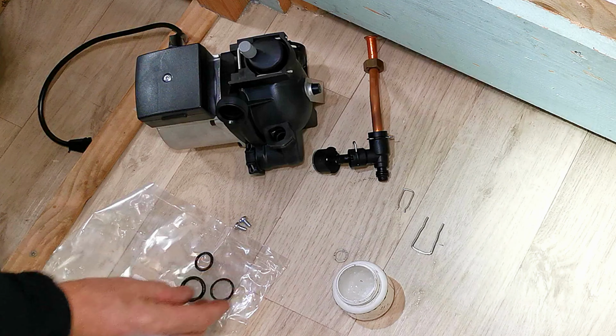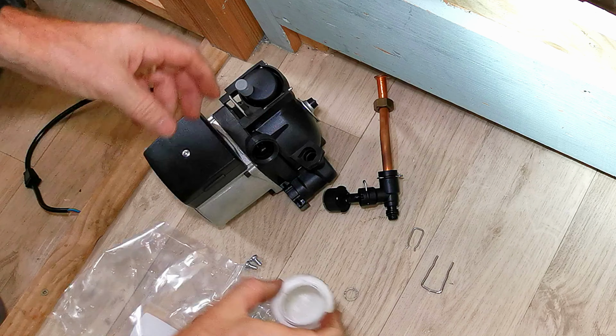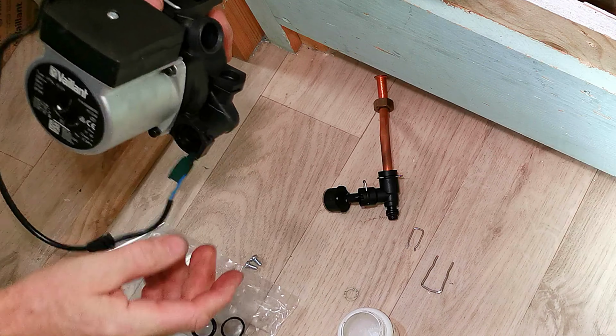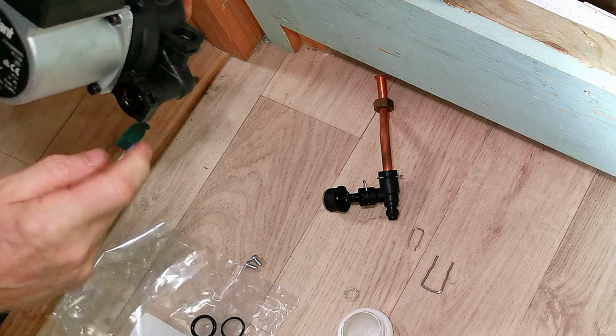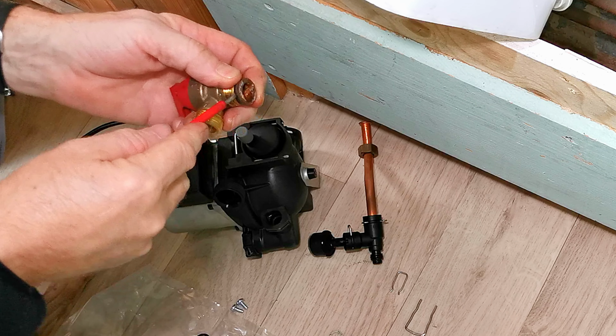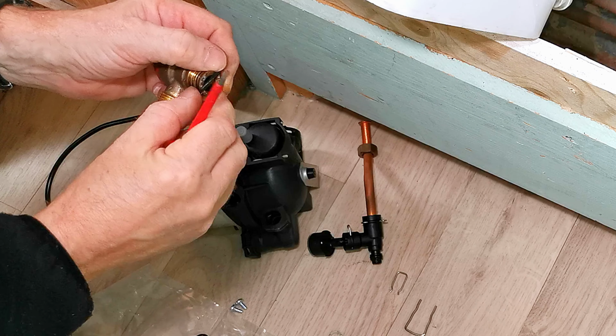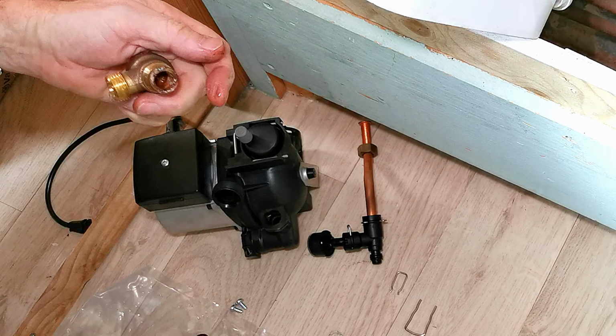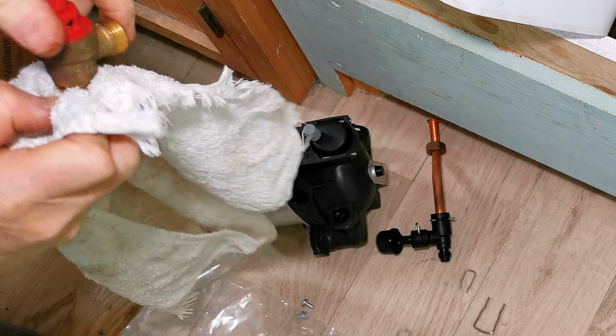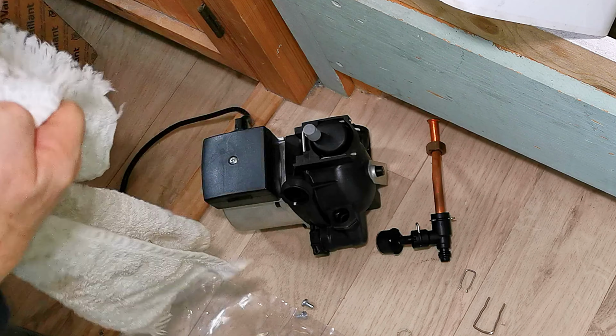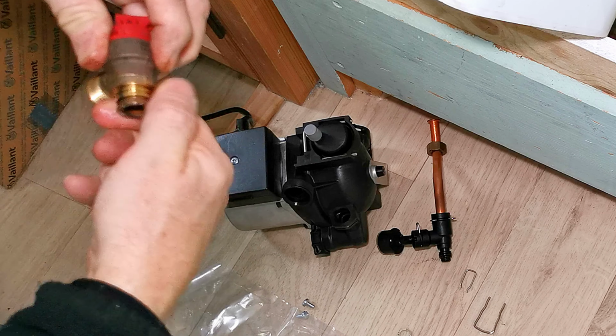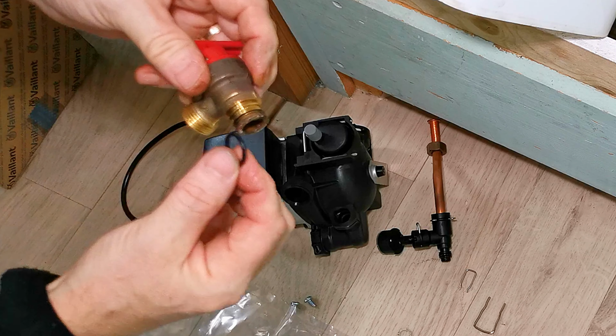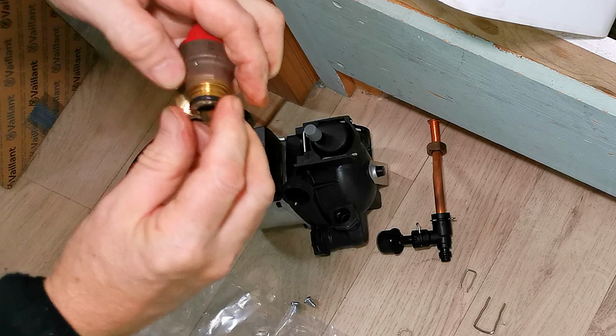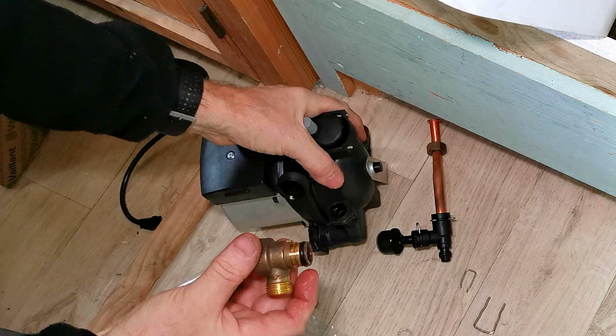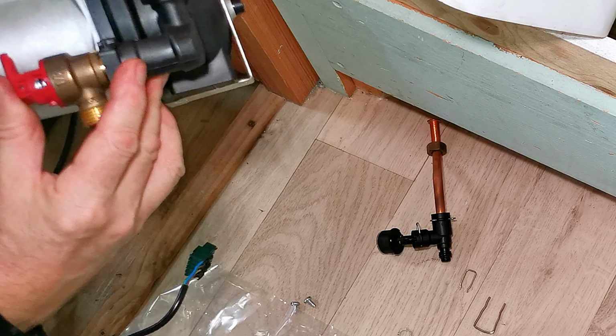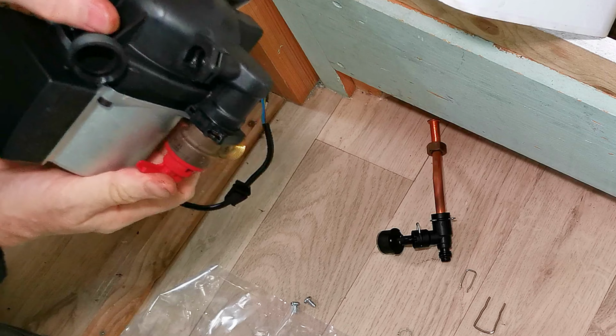I'm then going to put some silicone grease onto all the connections on the pump housing to make sure everything slips together nice and easily. And I get a good seal and there's no leaks. So now I'm going to get the pressure relief valve and remove the old O-ring from that. There we go, that's that old O-ring, put that in my bin box. I'm then just going to give it a clean before I apply some silicone grease. And there we go, I just put some grease onto that pressure relief valve, and then I can put the new O-ring onto that. And there we go, slip that onto there, then that's ready to go. I'm now just going to give it a quick test, make sure it slips in nice and easily into the pump housing, which it does, and there we go.